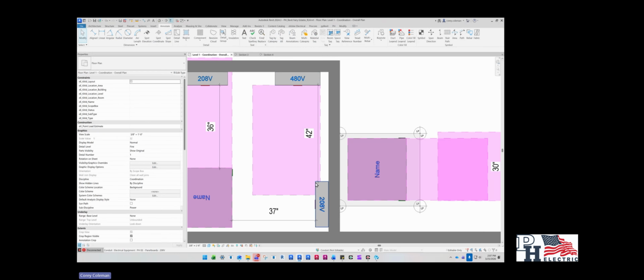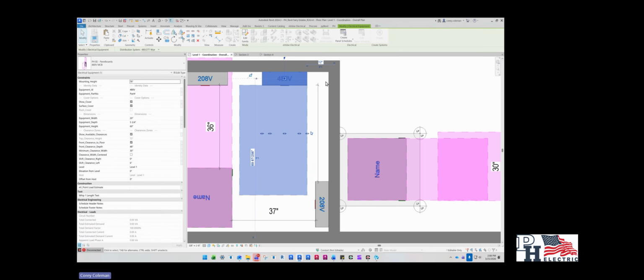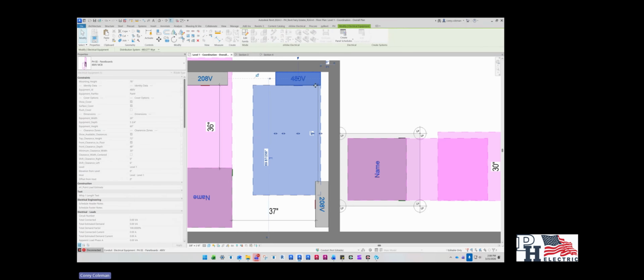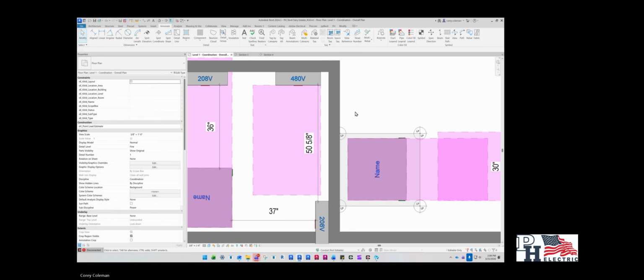Anytime there's even a little bit peeking into that clearance zone, this panel is now live parts to live parts. You have to consider it as 48 inches. So this panel cannot live here. You'd have to move this panel over so you can reduce the width, reduce the depth of the clearance, or you would have to move this panel further down away from it.